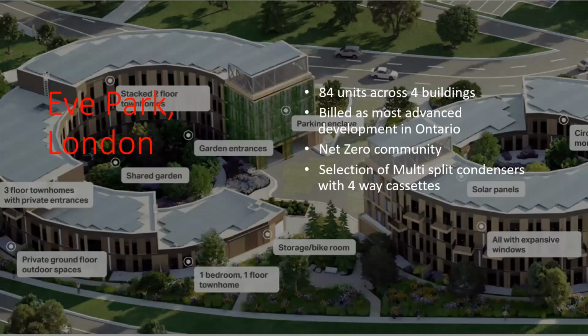Eve Park, London, 84 units across four buildings. This is a very technically advanced project where there's a panel inside each suite. So they have access to valet parking, I think remote bicycle storage, obviously security systems, and your heating and cooling system is going to be monitored through that system as well. And they went with multi-split systems because these are multi-story units, and they have 3/4 and 1-ton four-way cassettes that are supplying the thermal conditioning for the spaces.